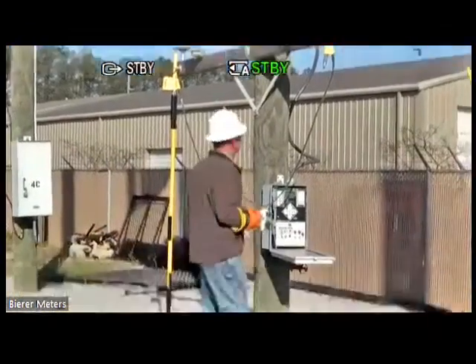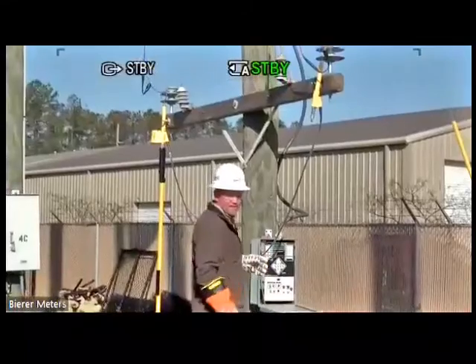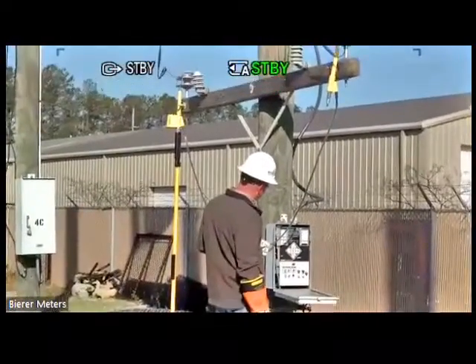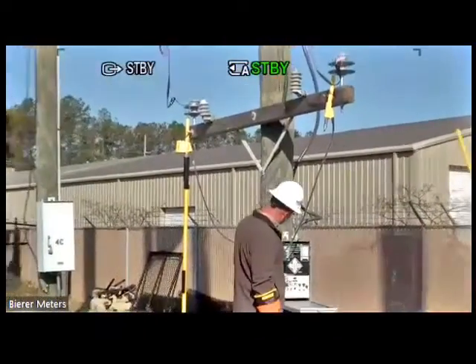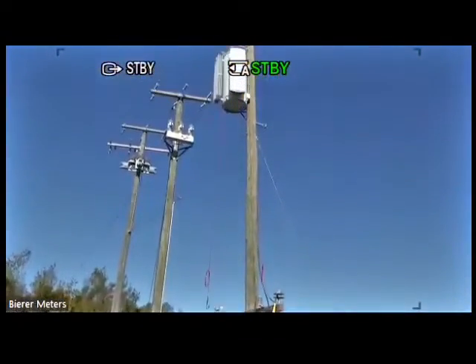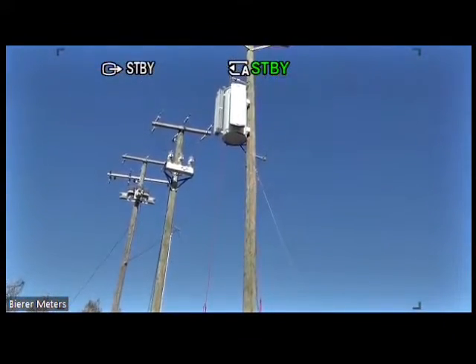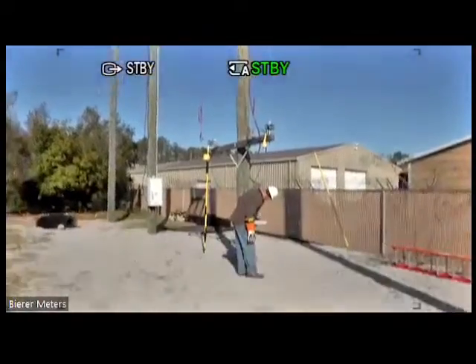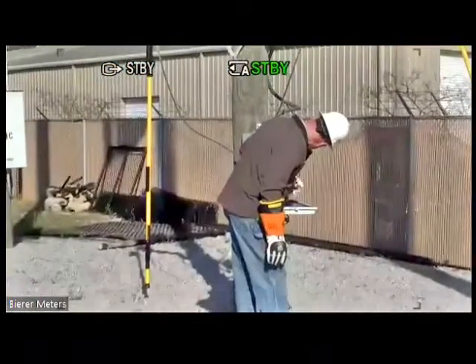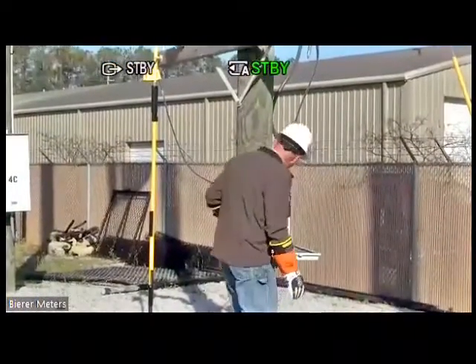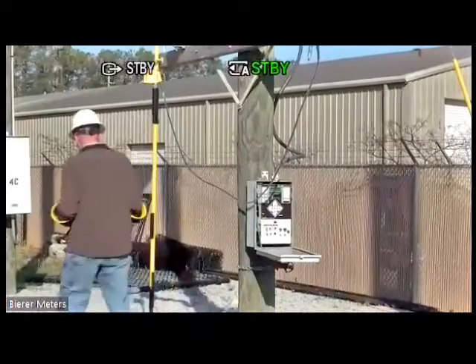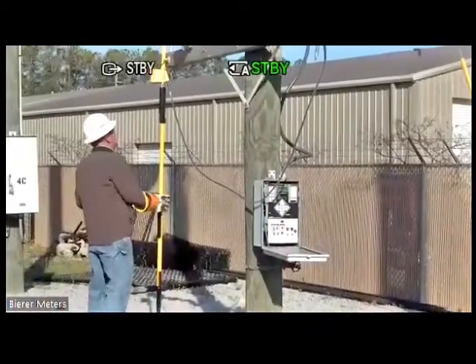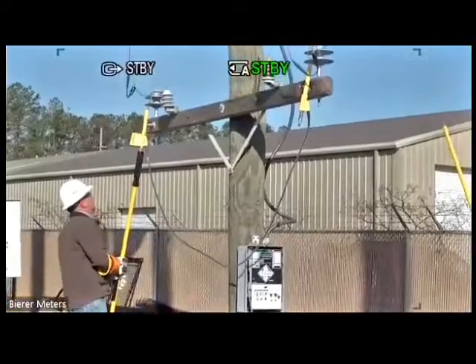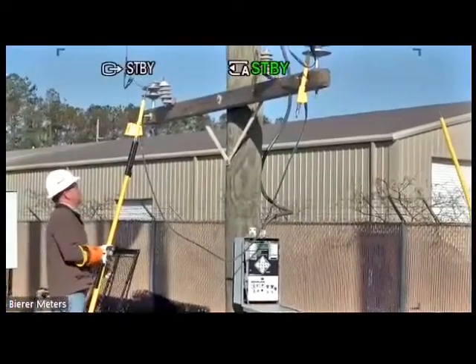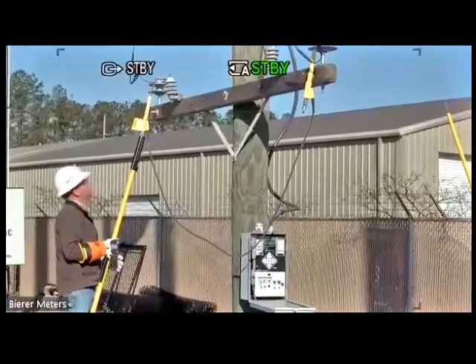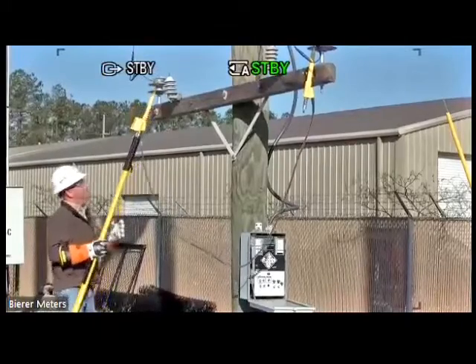So I'm down here on the ground. This regulator is way up in the air. I'll get Ryan to show you where this regulator is physically at. So it would be actually hard for somebody on the ground to see that dial on that regulator to see if it's in step or out of step. They would have to rely on this light inside the controller. And again, that's a little bit risky because what if the light burns out? Again, what if it fails? There could be a lot of things going on there.